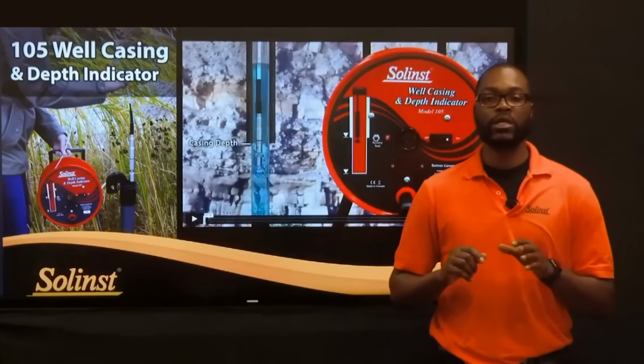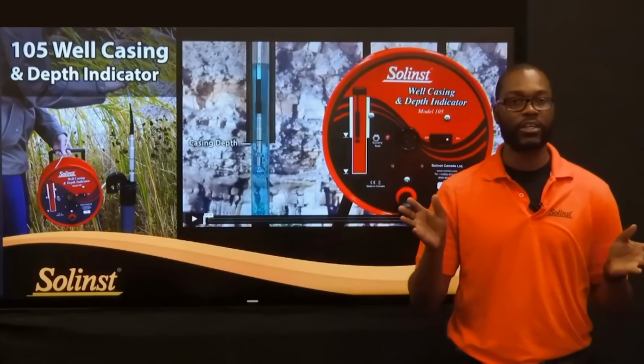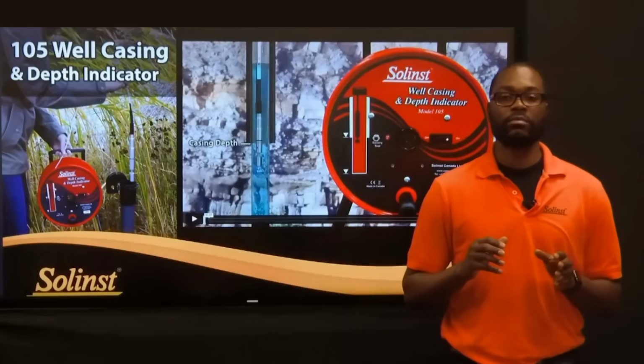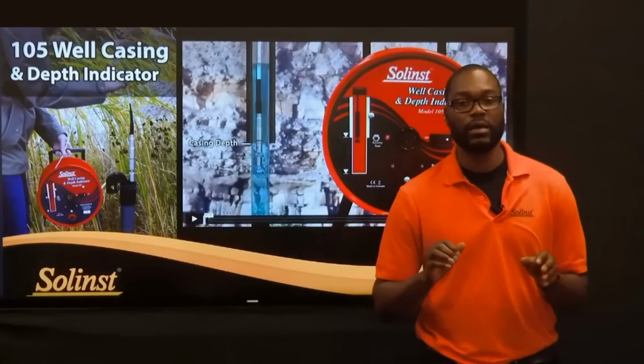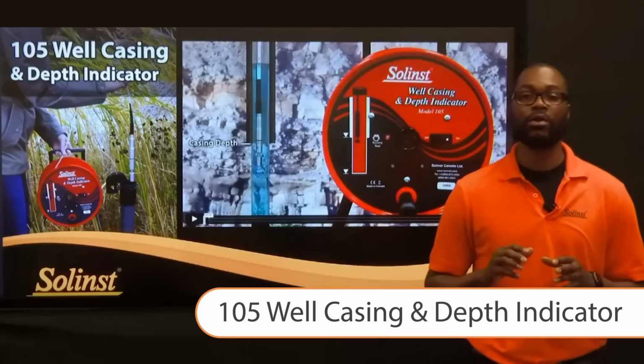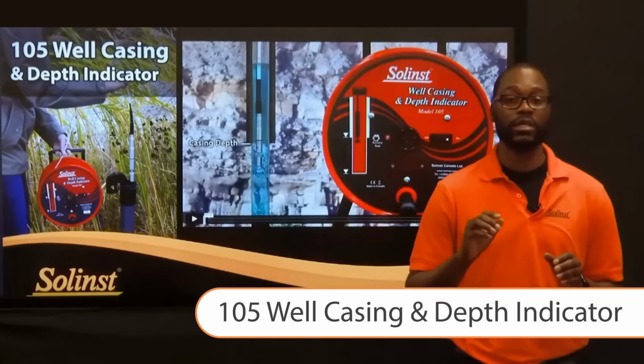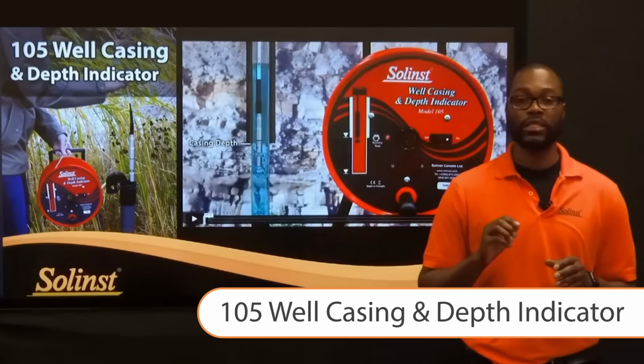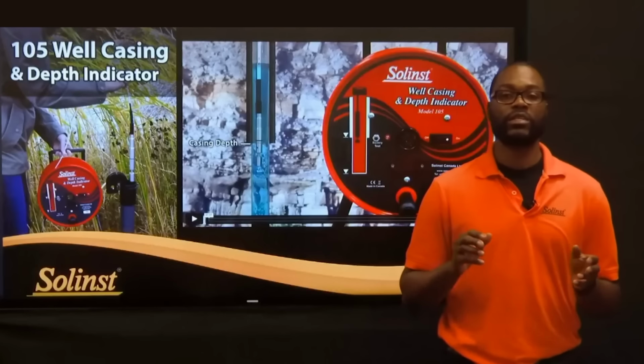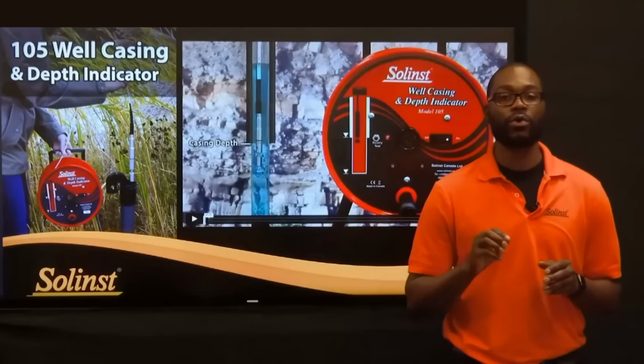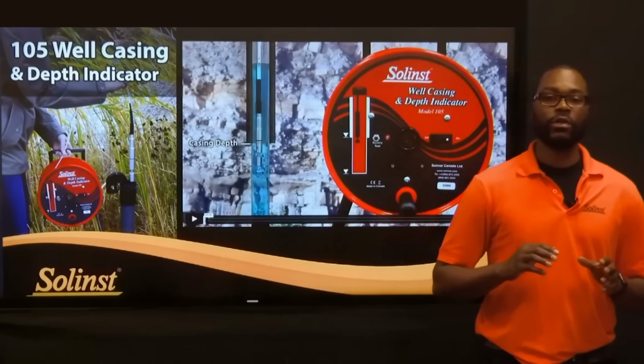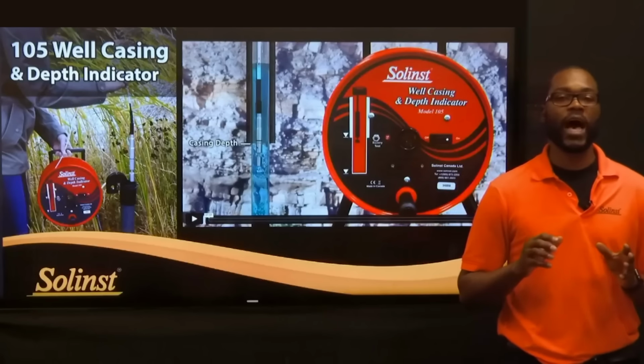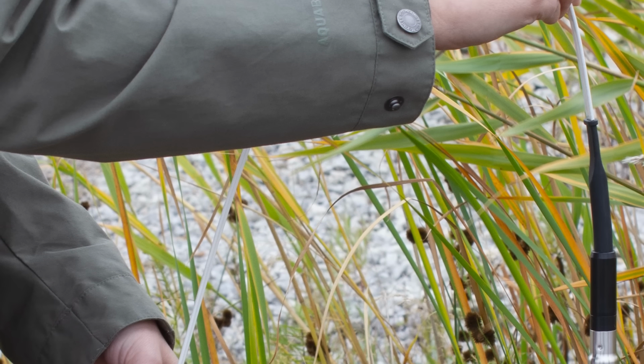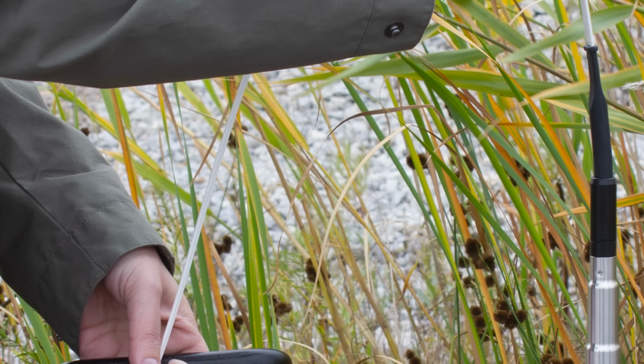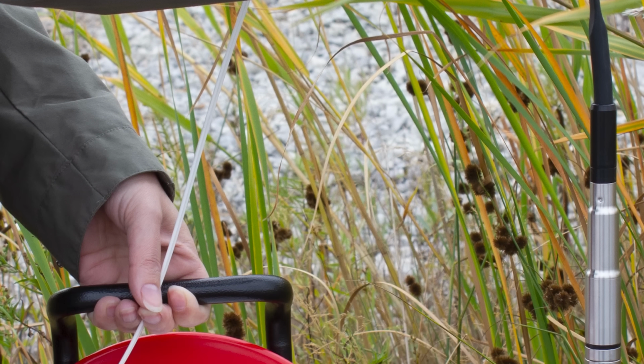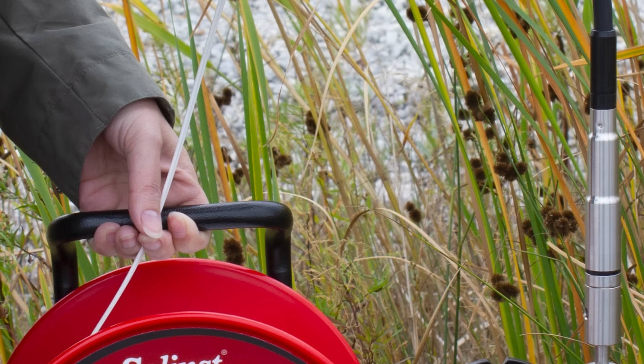Need to know where your metal well casing is broken or fractured? Do you need accurate measurement of total well depth at the same time? Look no further than the Solinst Model 105 well casing and depth indicator. It accurately measures well casing cracks, fractures, and breaks while also accurately measuring total well depth. The unique design is extremely tough while providing the same level of accuracy you've come to expect from other Solinst level measurement devices. The dual function probe has a strong internal magnetic assembly which helps to detect well casing.